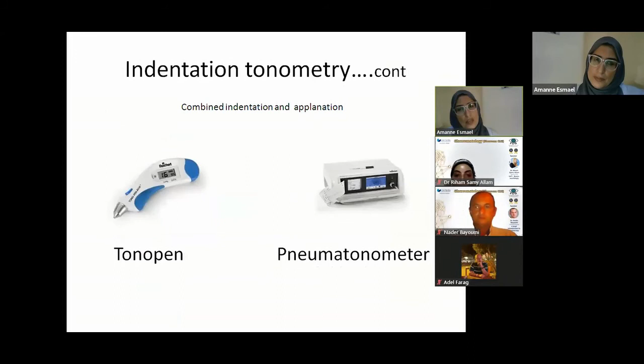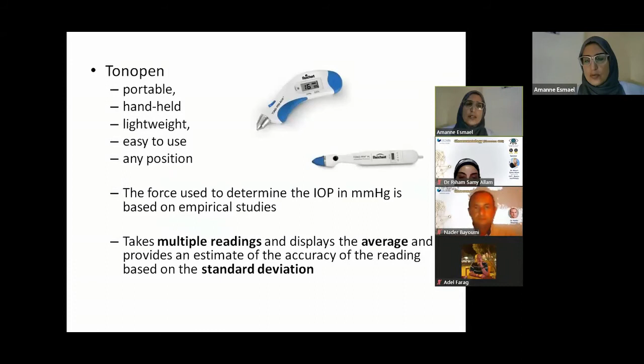Other indentation tonometries include the Tonopen and the pneumotonometer. The Tonopen is another portable handheld device that is lightweight and easy to use. Additionally, you can use it either in the upright position or in the lying down position. But you have to remember that the force used to determine the intraocular pressure by this device is based on empirical studies. Hence, the device itself will take multiple readings for you and display an average with a standard deviation to give you a clue whether to take this reading into consideration or not.